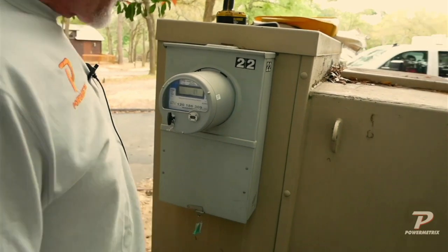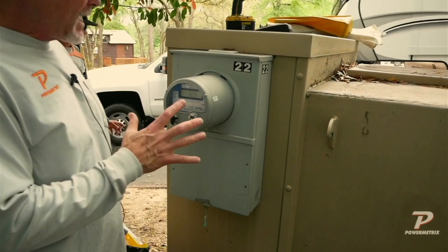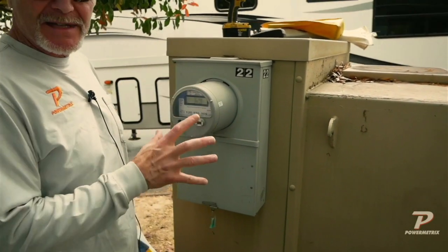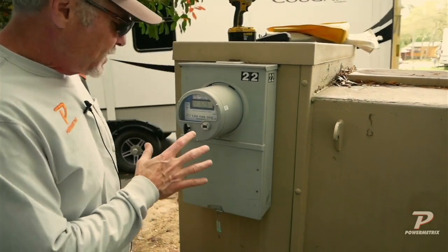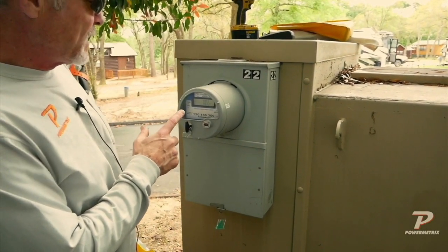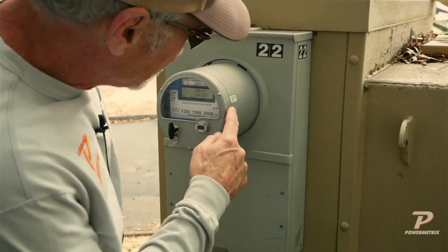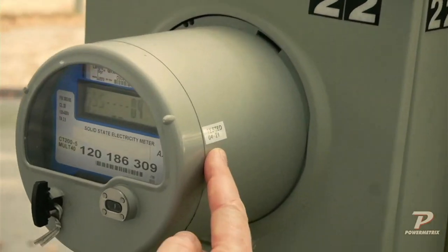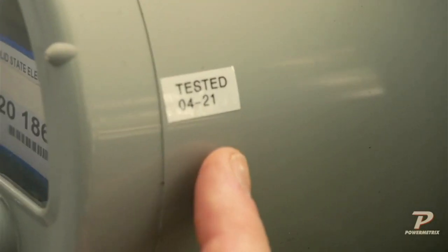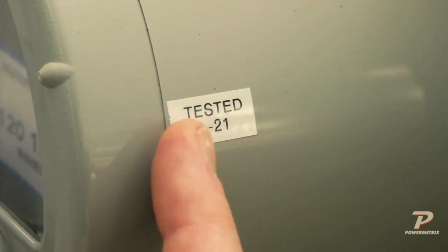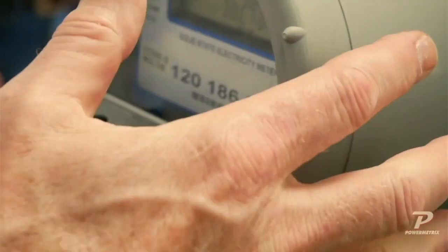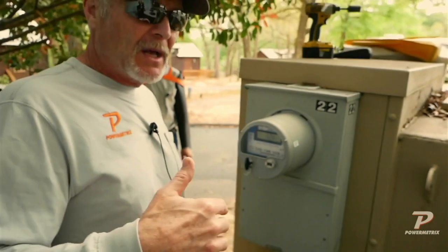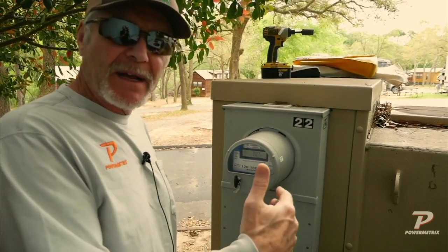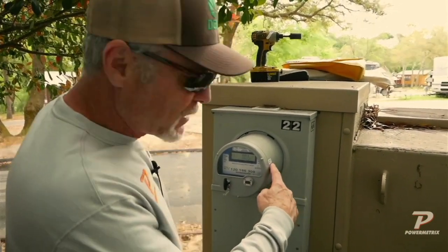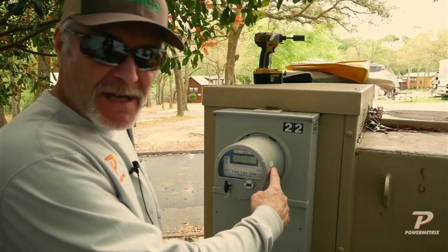Typically on pad mounts you'll see the meter can mounted on the outside of the transformer. One thing I like is they'll put a sticker on the outside showing the last time it was tested—we've already pre-stickered it, and you can see it says we're testing it today. So if an engineer from the office or anyone else comes out to look at it, they'll know right away when it was last tested.